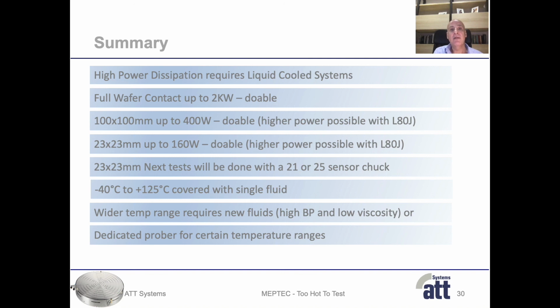A few words regarding the thermal fluid. At this point in time, we can cover a temperature range from -40 degrees C up to +125 degrees C with a single fluid. A wider temperature range requires a thermal fluid with a higher boiling point and lower viscosity at low temperature. Existing fluids offer either a high boiling point or low viscosity at low temperature. So this means that we need to develop new thermal fluids to cover a wider temperature range. Or alternatively, we need to dedicate the test cells for certain temperature ranges.